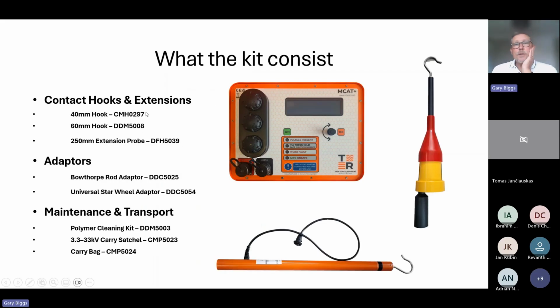So what does the kit consist of? Well, as I said, we've got the main box here, which has the controls, and it's the brains of the tester. We have an earth lead that comes out of here, which connects to the earth. We have the HV probe, which is this probe here, that we use to connect to the cross member. And then lastly, we have this part here, which is the hook that hooks over phase 1, phase 2, phase 3, and communicates with the MCAT, which would identify on the MCAT which phase had broken down, and therefore which insulator is the one that needs to be looked at.